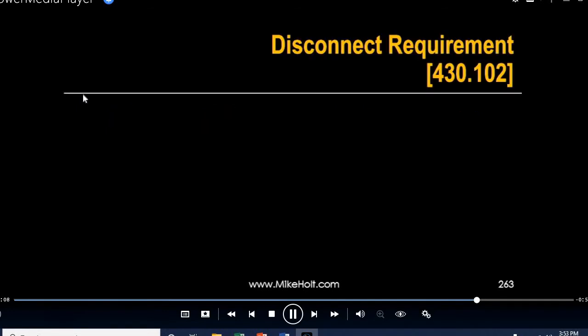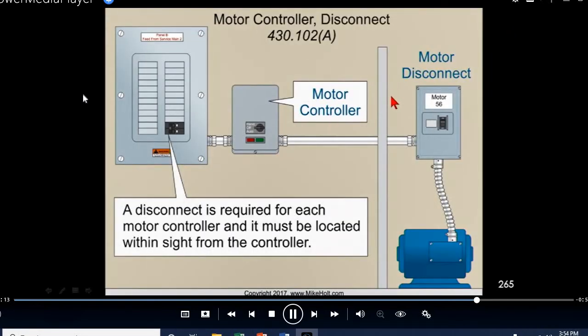Disconnecting means requirements in 430.102. Motor controller disconnect. Now, a motor controller is what makes and breaks the contacts. A disconnect is required for each motor controller, and it must be located within sight from the controller. So here's your controller, and the disconnect is right here, within sight of the controller. So that's fine.